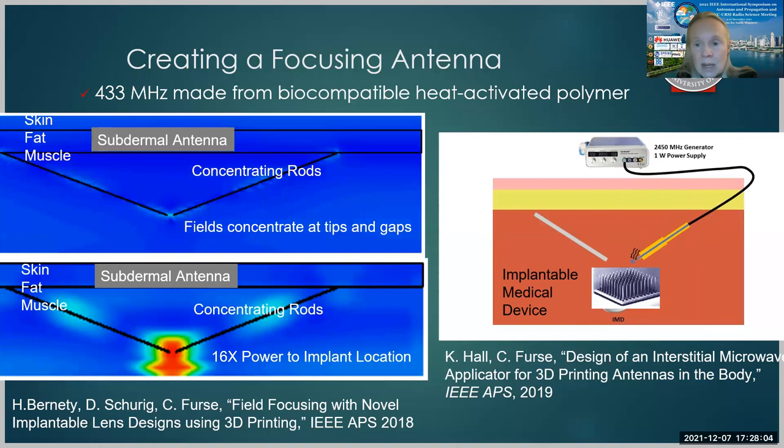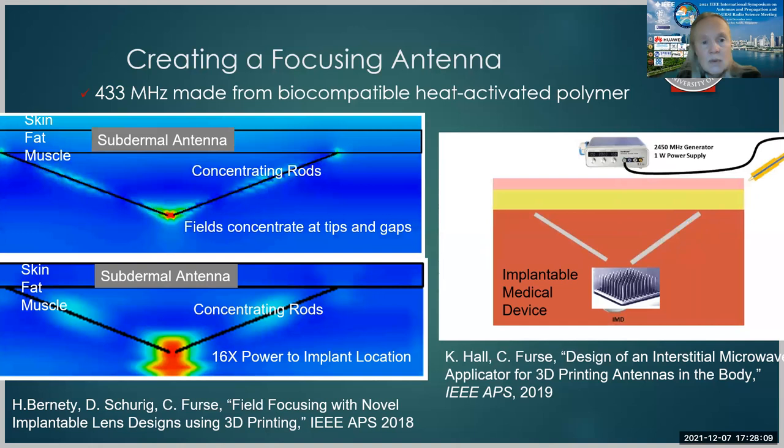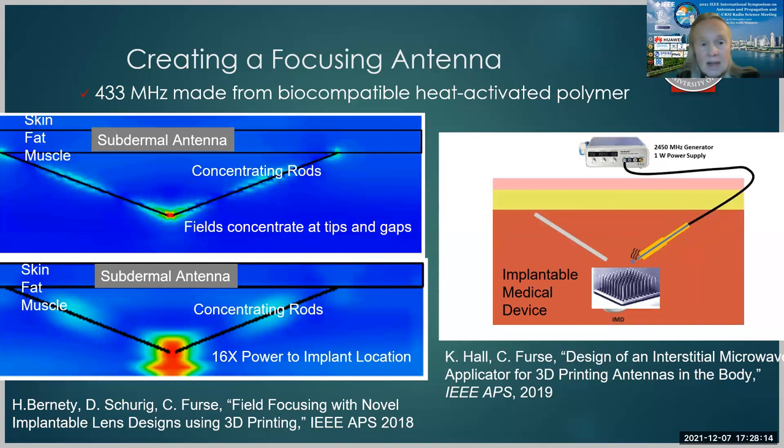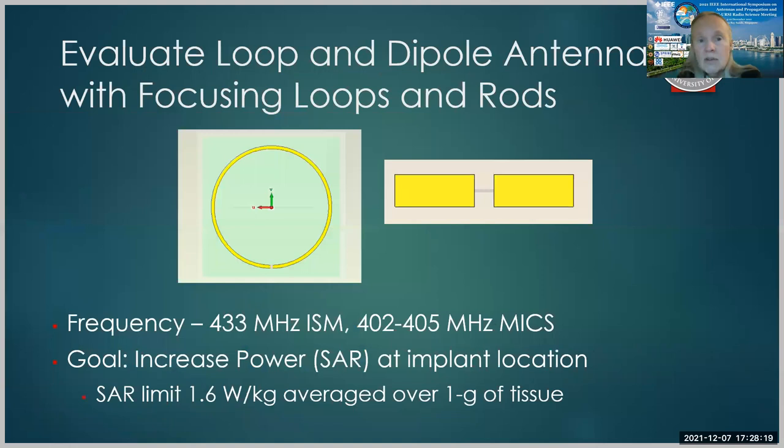Now the designs that we have done in the past, we've assumed that either we've evaluated what would happen if you had a plane wave outside the body. In this particular presentation, I'm going to talk about two different types of realistic antennas that would be used in the body. So one is a loop antenna, shown here, the other is a dipole. So instead of just considering how these focusing rods might work if we had a plane wave, let's see what would happen if we had a loop antenna outside the body and a very tiny loop on the implant, or a dipole outside the body and a very tiny dipole on the implant. And we're going to look at 433 megahertz because that's a frequency that we could test in our labs that is very close to the 402 to 405 megahertz MICS band.